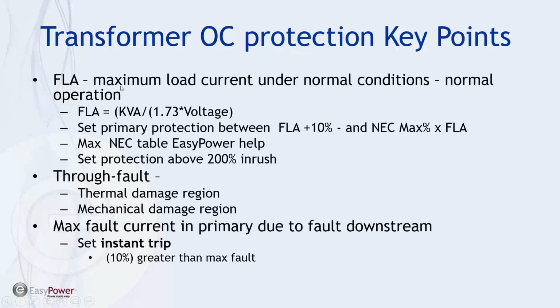One thing we want to make sure we're cognizant of is when we're adjusting primary protection, we want to make sure it's not sensitive to the inrush current when the transformer is first turned on, because it would cause nuisance tripping unnecessarily. Then the through fault curves have a damage region and a mechanical region, and that's what we're going to be aligning protective devices with, comparing them on the TCC curves. And then, as I mentioned, the only system above the motor circuit protectors that has an instantaneous trip would be the main primary relay, because we can determine what the worst case current will be. And we determine that and then set an instantaneous trip somewhere around 10% above that.